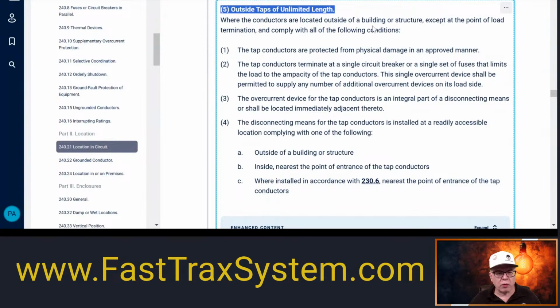So this is 240.21(B)(5). And again, jumping back and forth between secondary conductors. And now we are back to primary. We're back to feeders. Okay. So we're talking feeder taps now. So we shifted gears from the transformer secondary, which previously we talked about the 10-foot secondary. Today we covered the 25-foot application when it comes to secondary conductors. Now we're jumping back to feeders. And again, some people will say it's so confusing, Paul, you're back and forth, but that's the whole purpose. That way, somebody coming to the video doesn't just come for one topic. We cover multiple topics, that type of scenario.